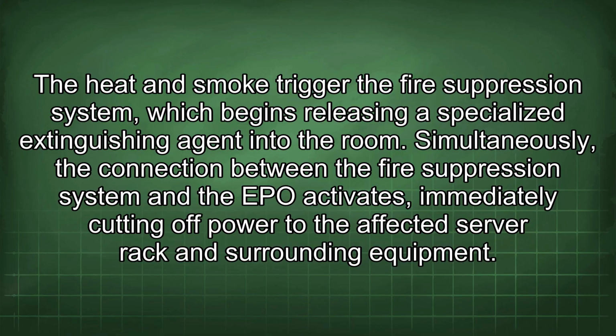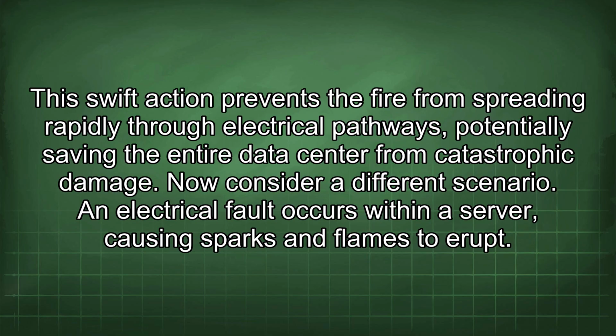Simultaneously, the connection between the fire suppression system and the EPO activates, immediately cutting off power to the affected server rack and surrounding equipment. This swift action prevents the fire from spreading rapidly through electrical pathways, potentially saving the entire data center from catastrophic damage.